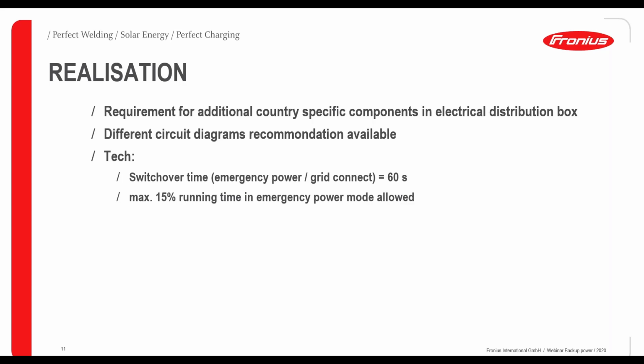What we want to make sure with that is that you use this system not in an off-grid system, but only in a grid connected system, because the semiconductors, the power module, is of course at a higher temperature when we run in off-grid mode. So we will probably have some issues with the long warranty terms of 7 years, as there could be a little bit more problems when you run in pure off-grid mode. So therefore we said it's not made for off-grid mode, it's made for an on-grid situation, but with some power cuts.